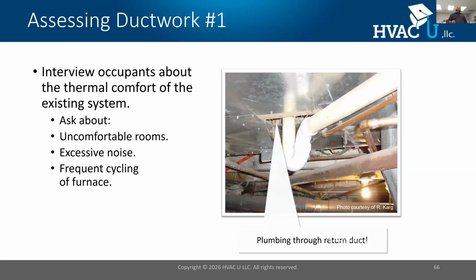What about noise? If I have a duct system that's really tight, oftentimes it's really loud. I've been in some customers' homes where the air handler is on and air is coming out of the duct system, and they have to turn the TV up just to hear the TV, right? So that lets you know that you have a problem. So you're going to ask about uncomfortable rooms, excessive noise, and then also about short cycling. If you see that kind of thing, obviously you want to pay attention to it.